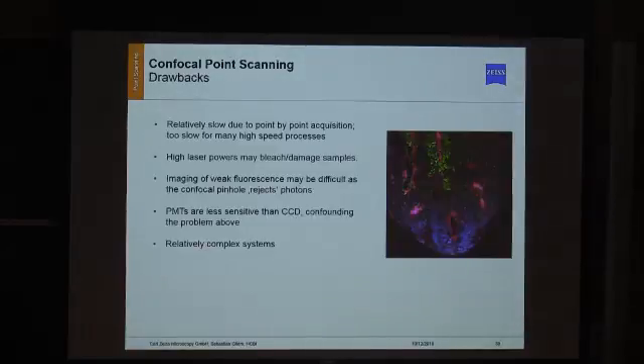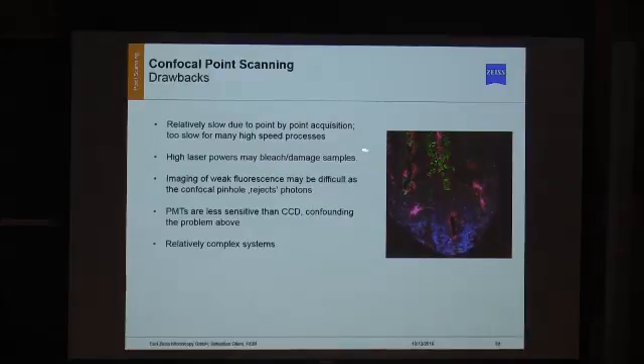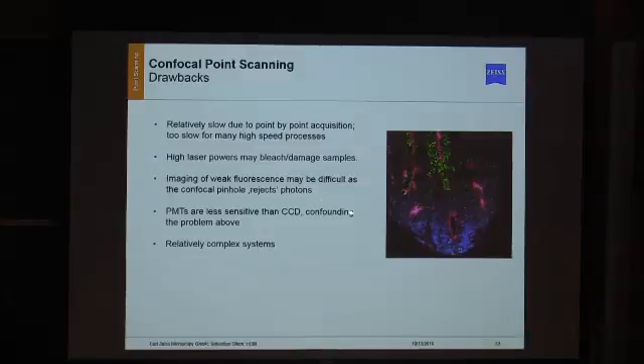The drawbacks of confocal point scanning microscopes: it's relatively slow because we scan point by point — widefield gets information from all points in one shot. Another disadvantage is that you typically use very high laser power, giving high light intensity per pixel, which can bleach or damage your sample. Imaging weak fluorescence is relatively difficult because the pinhole blocks much of that weak signal. Also, the PMT detectors used in confocal systems are generally less sensitive than camera-based CCD or sCMOS systems, which compounds the problem.